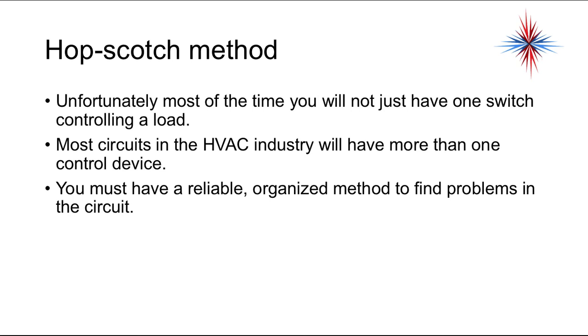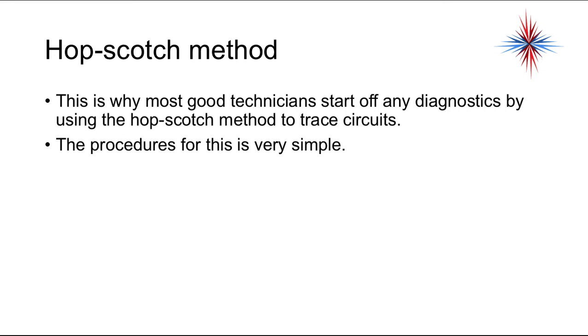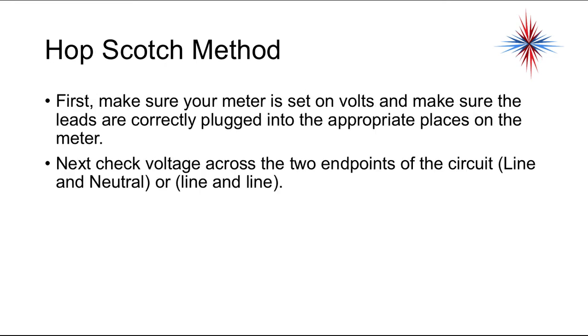Now, you'll often hear things referred to as the hopscotch method of checking for breaks and troubleshooting systems. Unfortunately, most of the time you'll not just have one switch controlling one load. Most circuits in the HVAC industry will have more than one control device. You must have a reliable and organized method to find problems in the circuit. This is why most good technicians start off any diagnostics by using the hopscotch method to trace circuits. The procedure for this is extremely simple.